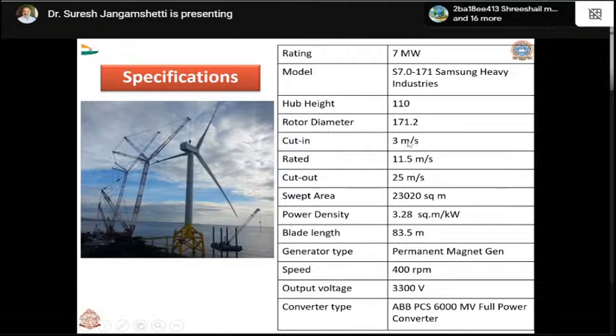3 meters per second, it would start generating electricity, and will generate up to 25 meters per second. 7 megawatts of power output will be given when 11.5 meters per second wind velocities are continuously blowing at that place. So this is the power density, blade length, then generator type - permanent magnet generator, speed is 400 RPM, output voltage is around 3300 volts, and converter type.